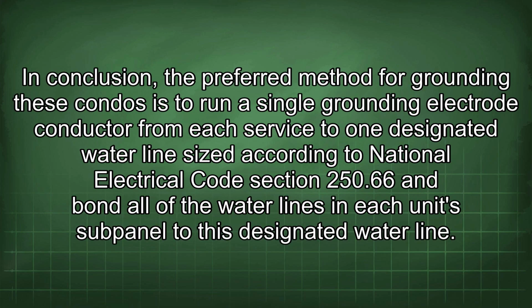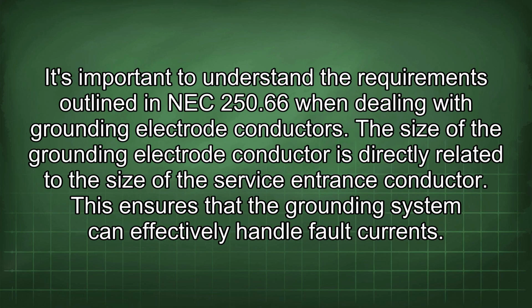In conclusion, the preferred method for grounding these condos is to run a single grounding electrode conductor from each service to one designated water line sized according to National Electrical Code Section 250.66 and bond all of the water lines in each unit subpanel to this designated water line. It's important to understand the requirements outlined in NEC 250.66 when dealing with grounding electrode conductors. The size of the grounding electrode conductor is directly related to the size of the service entrance conductor. This ensures that the grounding system can effectively handle fault currents.